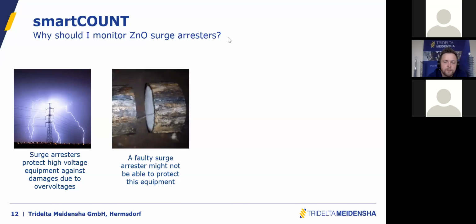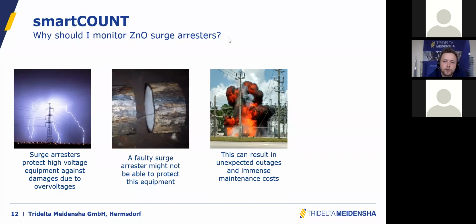This might be a seldom case, and you will say, okay, it's such a seldom case, so it doesn't matter. What should happen? If the surge arrester is faulty and the MOV block, maybe 1 or 2 MOV blocks are defective or degraded or whatever, the surge arrester maybe is not capable to protect your primary equipment in the next incident when a lightning strike hits the line, or we have switching overvoltage on the line. So what could happen is that the insulation of the transformer is broken, and of course this is a very drastic picture, but this is something which could happen if the insulation is broken, and you don't want your transformer to break down or explode. Of course, this will lead to maintenance cost and also to blackout, and you want to prevent this.